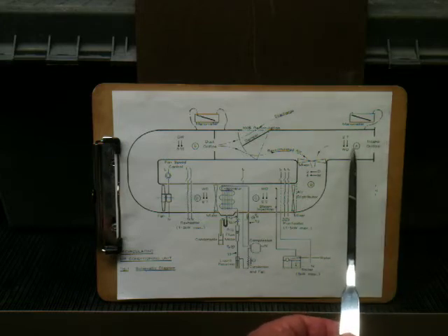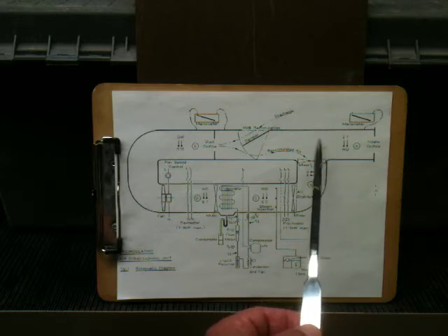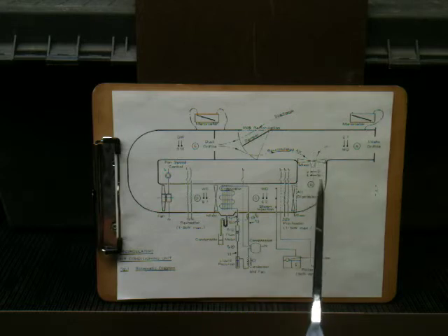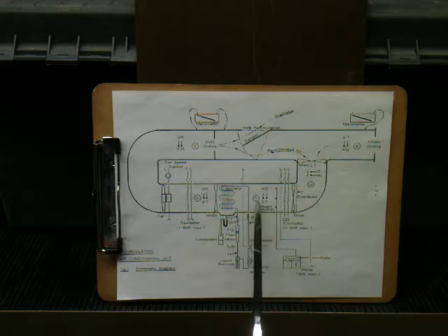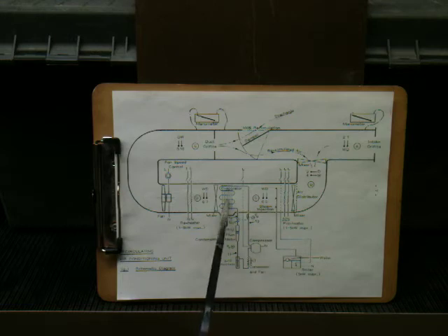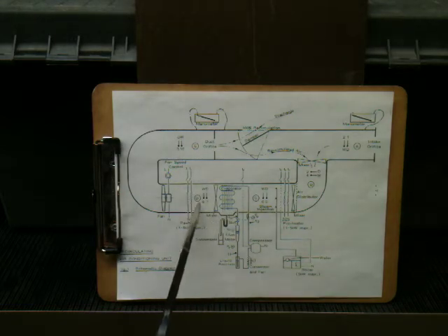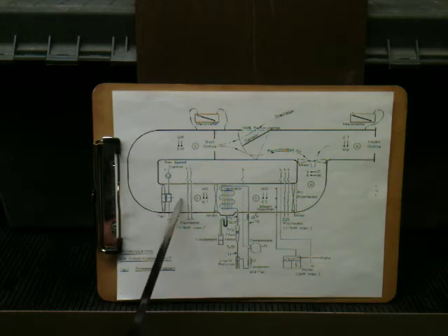Air flows past station A, wet bulb, dry bulb, travels downward through a mixer, past station B, through another mixer, past the preheater, which is controllable, past the boiler, which is controllable. Then we have station C. Then we go through the evaporator of the refrigeration cycle, which is controllable, another mixer, and then at station D, again, we have wet bulb, dry bulb. We go past the reheater.